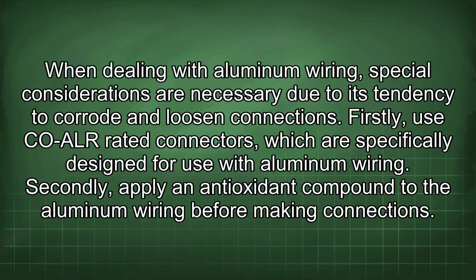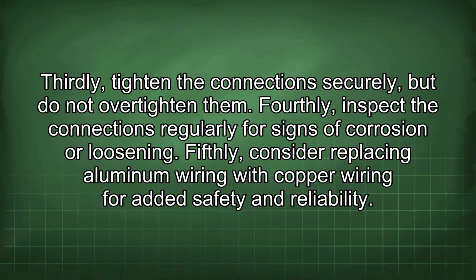When dealing with aluminum wiring, special considerations are necessary due to its tendency to corrode and loosen connections. Firstly, use CO-ALR-rated connectors, which are specifically designed for use with aluminum wiring. Secondly, apply an antioxidant compound to the aluminum wiring before making connections. Thirdly, tighten the connections securely, but do not over-tighten them. Fourthly, inspect the connections regularly for signs of corrosion or loosening. Fifthly, consider replacing aluminum wiring with copper wiring for added safety and reliability.